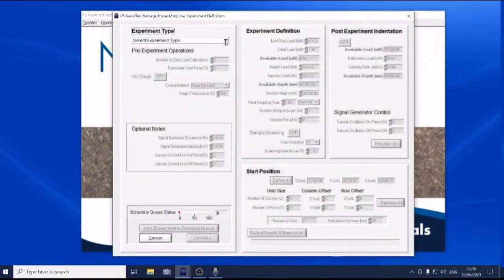So let's go to our first menu here. We select the experiment type. There are a variety of different tests that come under the name impact. The one we're actually doing today is called multiple impulse. So a multiple impulse test involves repetitively accelerating a test probe at a sample surface, and then pulling it away again. So we're going tap, tap, tap, tap, tap on the sample surface. You can understand why in the past we've referred to this as a woodpecker test.